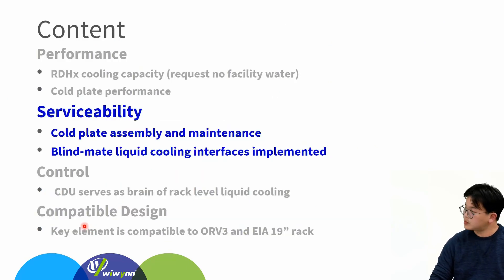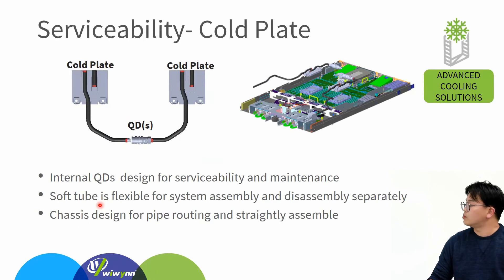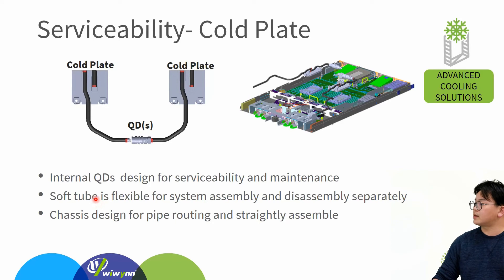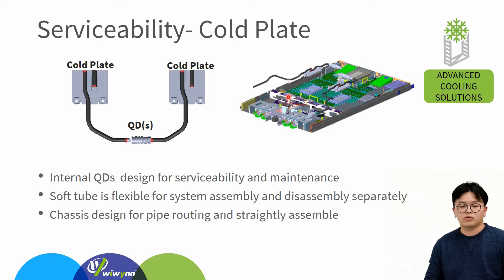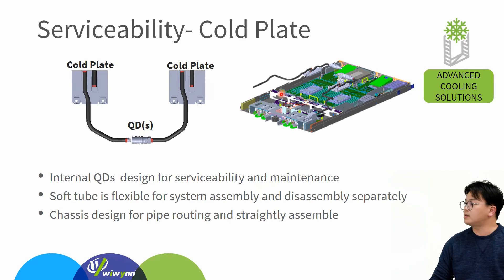This next design factor is for serviceability. To ensure cold plate maintenance is easy to assemble, we plan to add an internal quick disconnector between the two cold plates and use a soft tube for system assembly and disassembly. After adding the internal quick disconnector, it becomes possible to maintain and disassemble a single cold plate separately, as shown in this photo. We also need to modify the chassis design for cold plate pipe routing to ensure we can assemble the cold plate straight up and straight down.